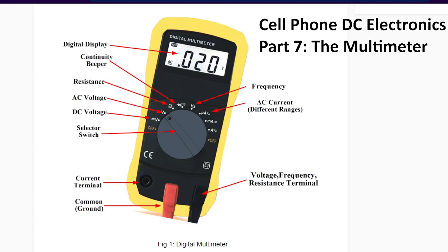In that setting also is the little sound waves. That's continuity, and that's the beeping. You've probably heard of this continuity mode before. It's pretty common. It's a good way of finding a short to ground. You put the red probe on your ground plane and your black probe wherever you're looking.